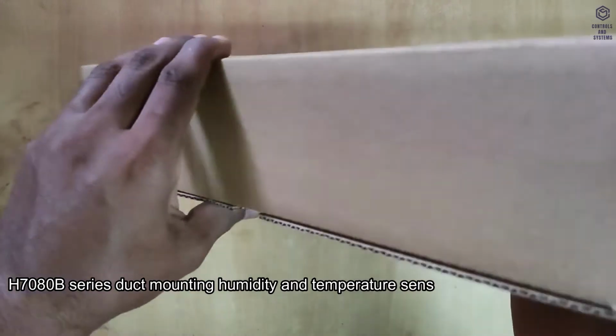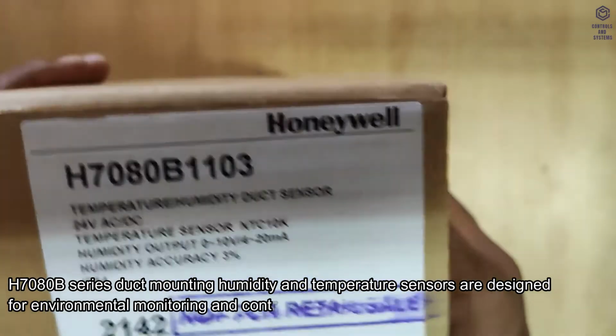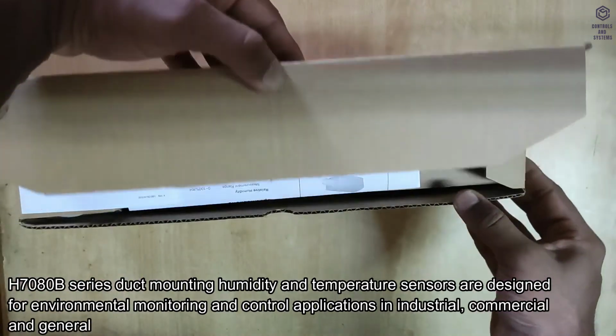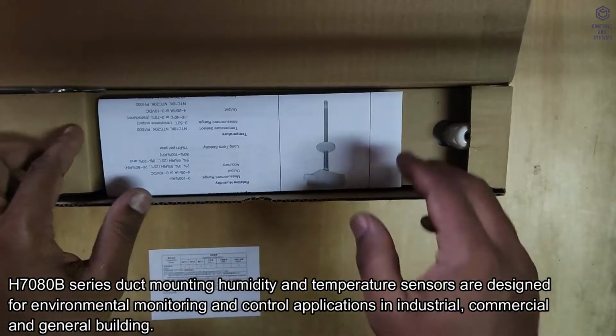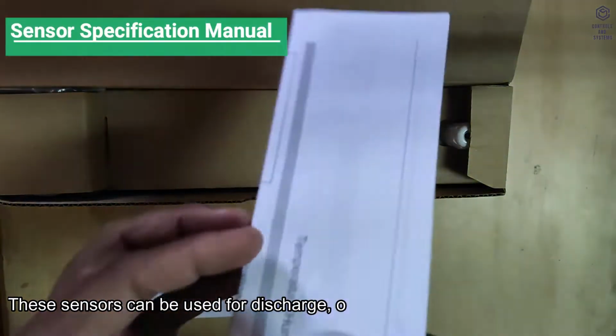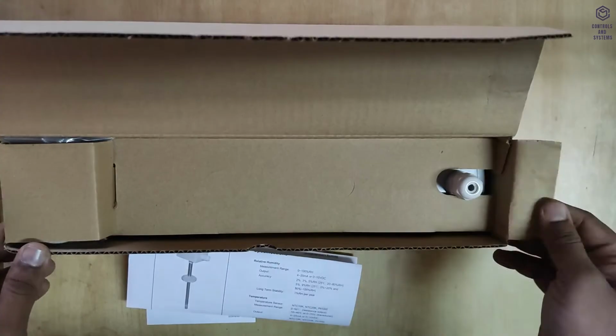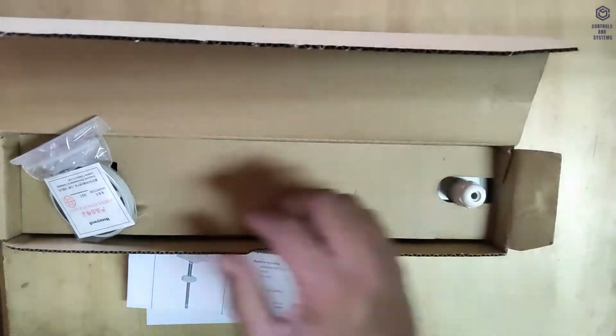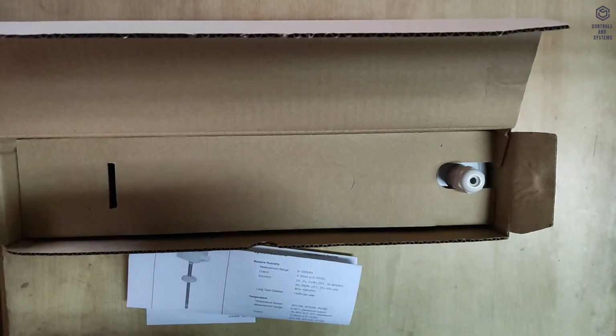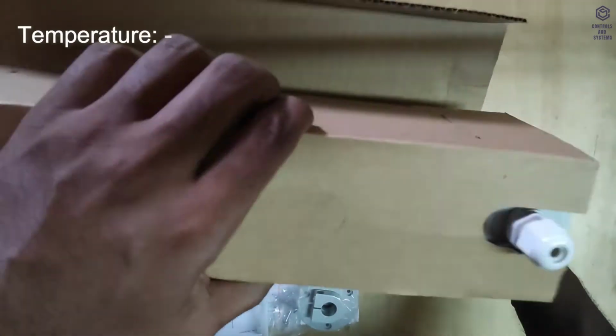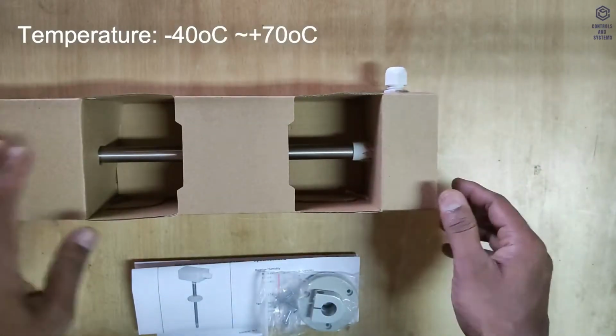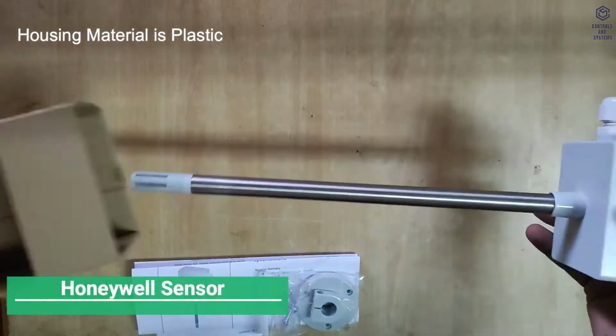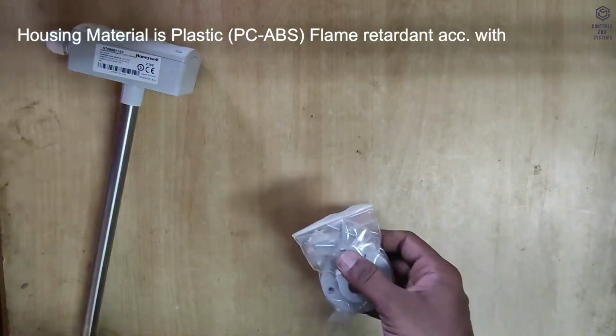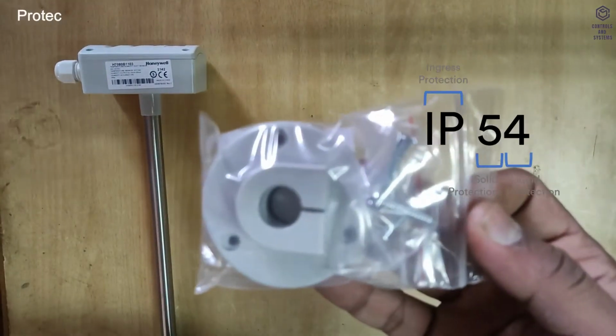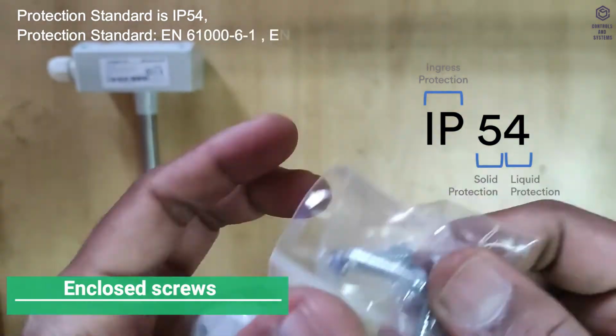H7080B series duct mounting humidity and temperature sensors are designed for environmental monitoring and control applications in industrial, commercial and general building. These sensors can be used for discharge or return air control. Sensor materials: sensor, specification, manual, screws, gasket, flange, cover, plug, base, filter. Storage temperature is -40°C to +70°C. Housing material is plastic, PC ABS, flame retardant, tested with UL94V0. Protection standard is IP54.